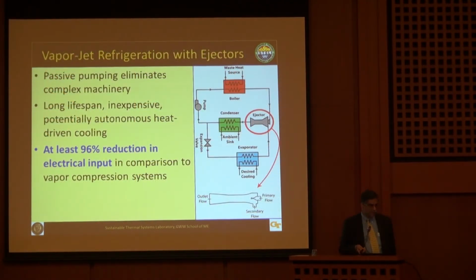Another way we're trying to achieve carbon neutral processes is vapor jet refrigeration with ejectors. Here there's a waste heat source, and usually you'd need a turbo compressor, but instead we use a vapor jet ejector. It has no moving parts: you take a high pressure fluid, send it through a nozzle, and it entrains the surrounding fluid and pumps it, replacing a turbine and compressor. My student is studying this both experimentally as a refrigeration system, and also running experiments to understand the supersonic processes happening inside.